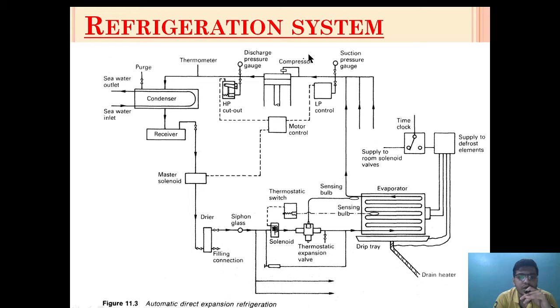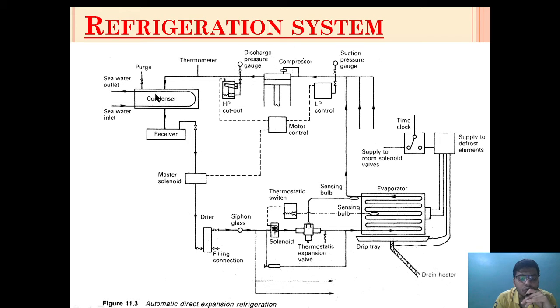Looking at the bigger system, the four components are: the compressor, condenser, evaporator, and expansion valve. Along with these, the system consists of various safety devices. The refrigerant coming out from the evaporator goes to the compressor, which compresses the refrigerant gas. An HP cutout is provided so that if the valve before the condenser is shut, the line does not get over-pressurized — to prevent that, the HP cutout safety device is provided.